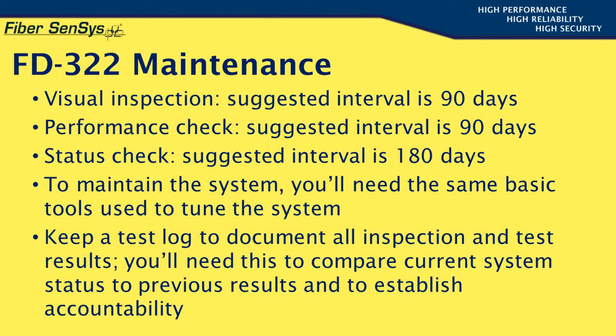In this training module, we'll discuss system maintenance issues. There are three basic types of regularly scheduled maintenance tasks that need to be performed on an FD322 system. These include visual inspection and performance checks, each with a recommended 90-day interval, and a status check recommended every 180 days. To maintain the system, you'll need the same basic tools used to tune it.